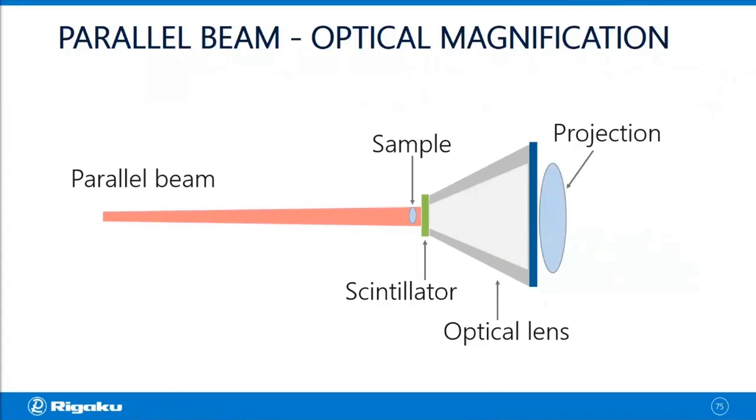And this geometry actually works very well for high-resolution imaging. But at the same time, it requires a high-power x-ray source. And that's because we are using only the parallel portion of the x-rays, and also you have to use a pretty thin scintillator to achieve high resolution.